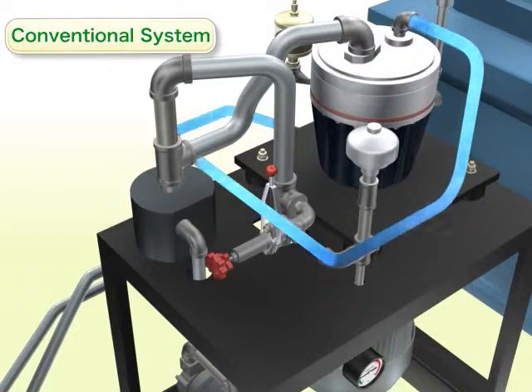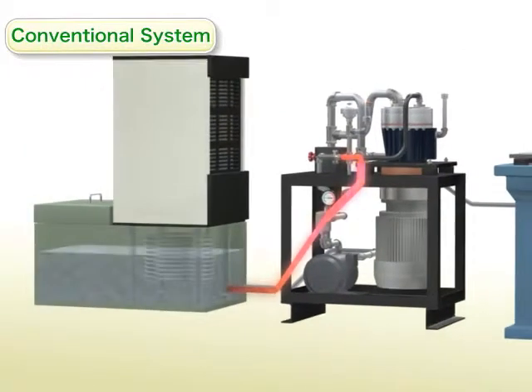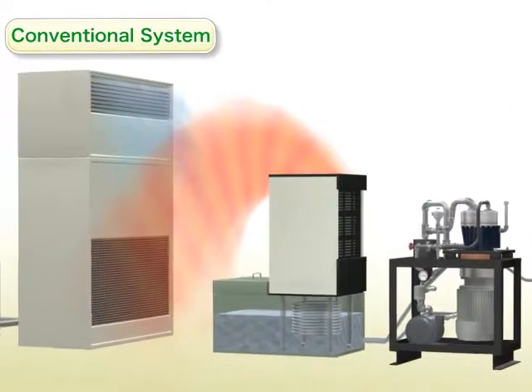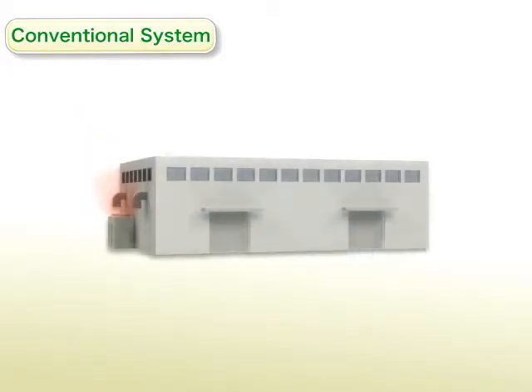With conventional systems, the energy contained in the coolant discharged from a vent of the bypass relief valve leads to a rise in temperature and requires cooling with an oil cooler. In turn, the heat emitted by the oil cooler into the room raises the room temperature, which has to be cooled by an air conditioner. Ultimately, the resultant waste heat has to be discharged into the environment. This is clearly a double or triple-fold waste of energy.